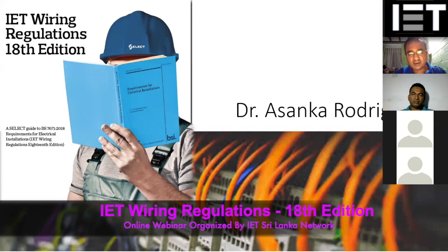Yeah, and the balance part of that question is, can SPD be installed at sub-distribution, inside the house panel, where earth cable length is about 10 meters long? Yeah, that is not actually the earth cable, because you have to connect SPD to your equipotential bonding bar. So the length to the equipotential bonding bar in total should be less than 0.5 meter. From the equipotential bonding bar to earth, you have to minimize the length as much as possible, because if there is an earth fault situation, due to the resistance of that conductor part and the earth electrode part, there will be a potential rise. So to minimize that, you have to minimize the resistance in that part. But other than that, there is no problem.